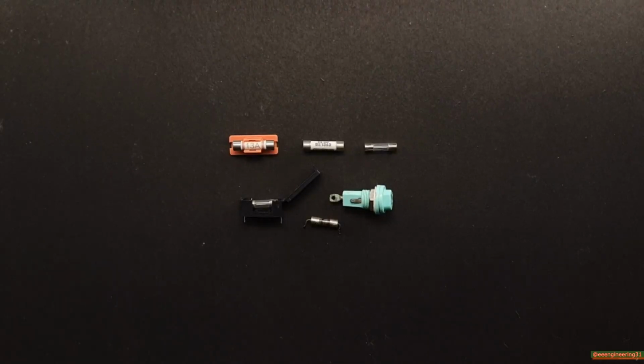The speed at which a fuse acts is also important in some devices. Time delay or slow blow fuses are used for applications like motors, which may require momentary high startup currents. Ultra-fast acting fuses are used with specially sensitive circuitry that must be protected from even transient overcurrent conditions. Most consumer electronic gear uses standard fuses, which are considered fast acting but not ultra fast. Also, fuses come in many shapes and sizes. You will find fuses in holders and also soldered directly to the circuit board.